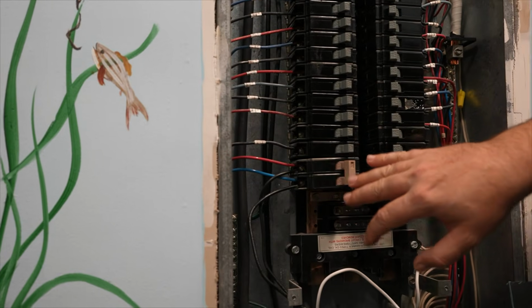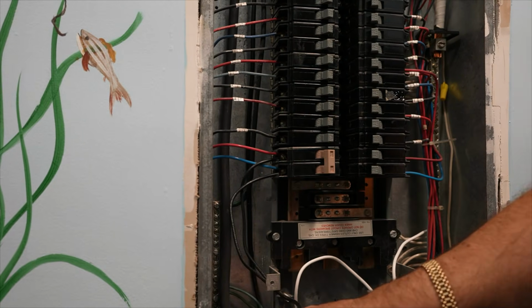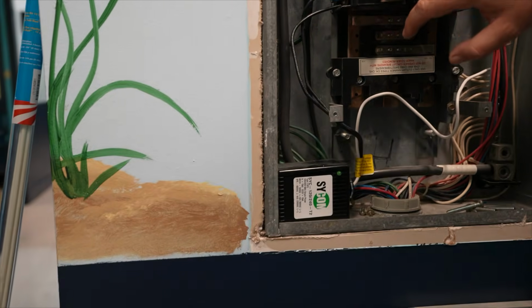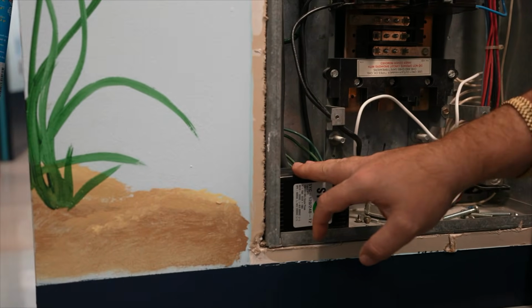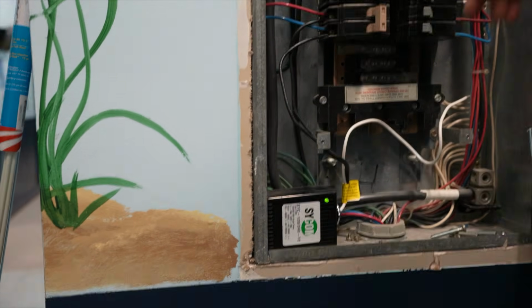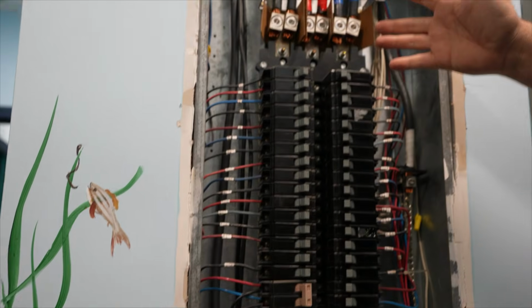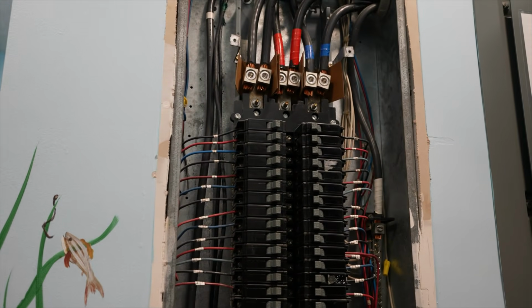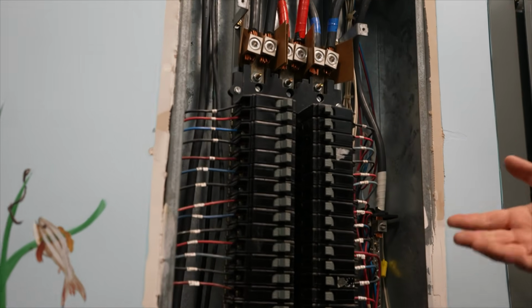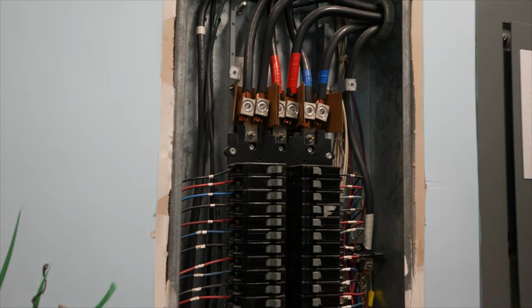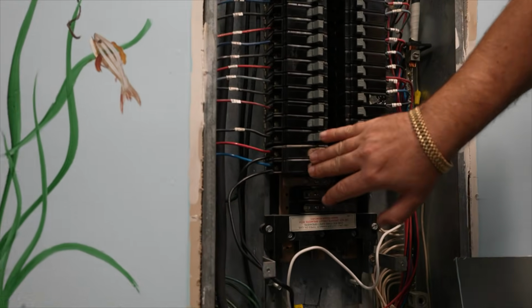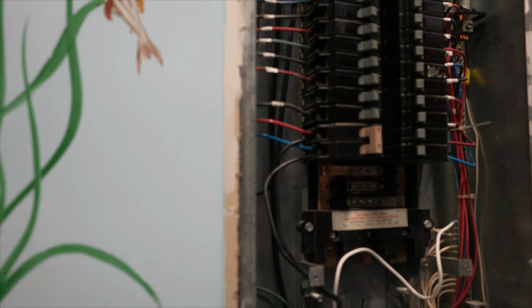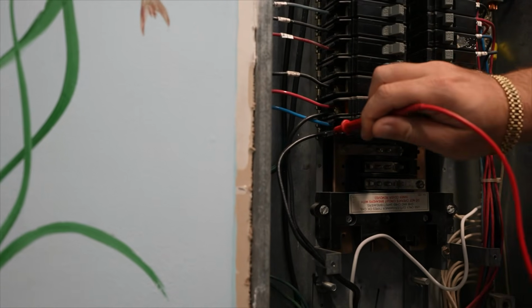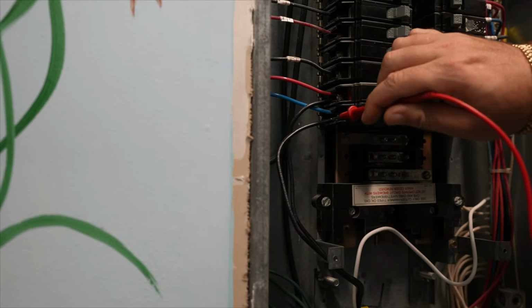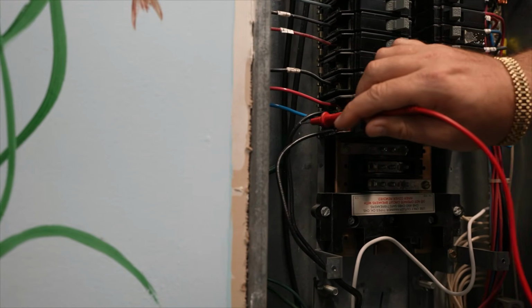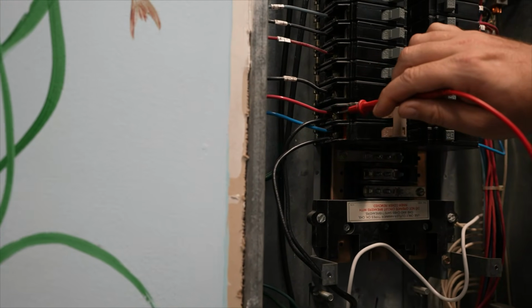I wanted to take a closer look at the situation here. This is a surge protector, and usually you want that to be as close as possible to where the feeds come in. Most manufacturers outline that on their installation diagram or directions. But here it's on the bottom, and there's two wires jammed underneath one screw - you've got the black wire and the blue wire under one screw, and the black wire and red wire under the other screw.